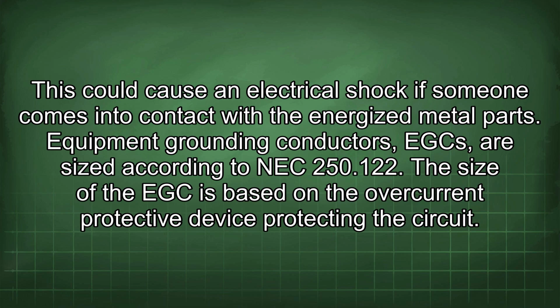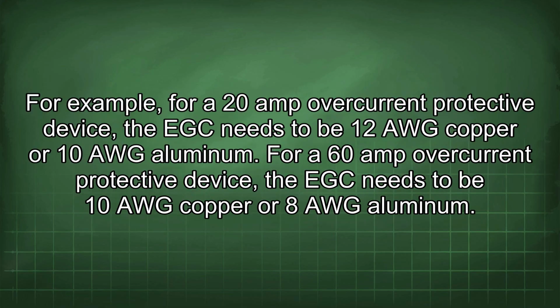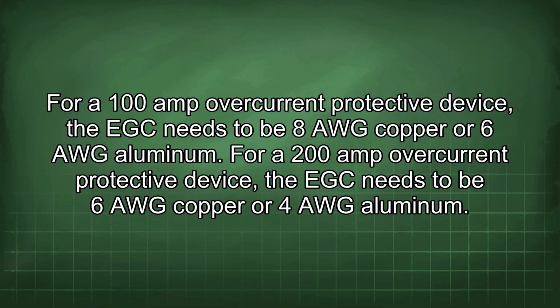Equipment grounding conductors, EGCs, are sized according to NEC 250.122. The size of the EGC is based on the overcurrent protective device protecting the circuit. For example, for a 20 amp overcurrent protective device, the EGC needs to be 12 AWG copper or 10 AWG aluminum. For a 60 amp overcurrent protective device, the EGC needs to be 10 AWG copper or 8 AWG aluminum. For a 100 amp overcurrent protective device, the EGC needs to be 8 AWG copper or 6 AWG aluminum. For a 200 amp overcurrent protective device, the EGC needs to be 6 AWG copper or 4 AWG aluminum.